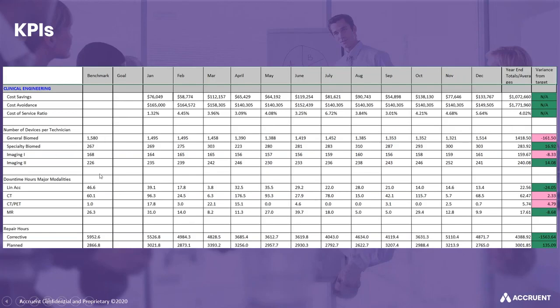Number of devices per technician we tracked, downtime hours for major modalities, and so again, going back to tracking metrics and reporting metrics, we wanted to make sure that we did report on that. And the number you see under this benchmark column is the total number of hours for all of the devices that we had in our inventory. So the benchmark for linear accelerator, for example, was a total of just under 47 hours. CT just over 60 hours. We had a lot of CTs in the system. We only had one PET scanner, so just 1 hour for that, and then MRI 26.